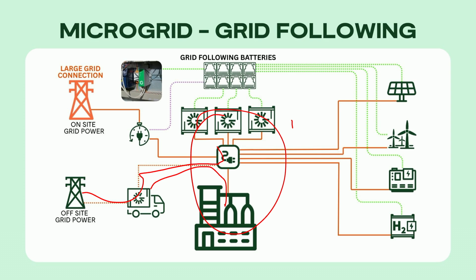Obviously, the energy will first try to go where it's needed. The batteries will ramp down if there's energy coming in, and if there's excess energy available, they will charge themselves with it. So one of the key components here is that the power of the energy being delivered needs to be more than the load in order to charge the batteries, otherwise you just slow down the discharge.